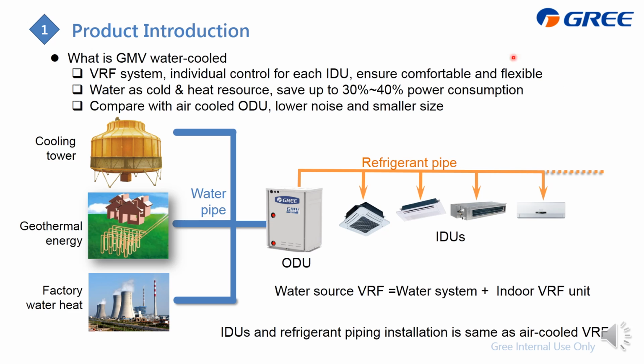On the other hand, the difference is the condenser side. For the air cool, we find that the pressure difference between the high and low pressure is too much, which leads to the system operating efficiency not being that high. So we considered, why not apply water to cool down the condenser? This can raise the system operating efficiency.